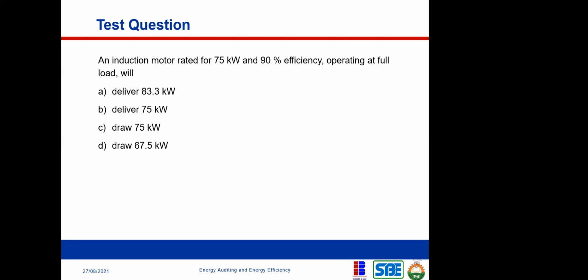Now, yes. When you pick up an electric motor and you look at the nameplate, it's going to tell you certain things. It's going to tell you the capacity of that motor in terms of kilowatts. The kilowatt they tell you is the kilowatt mechanical output of that motor. Okay? And they're also going to tell you the efficiency of that motor. So if they tell you that the efficiency of that motor is 90%, that efficiency of 90% is at full load. So they will tell you that when that motor is operating at full load, at 90% efficiency, that motor is going to give out 75 kilowatt mechanical shaft power. This information is going to be there in your nameplate.